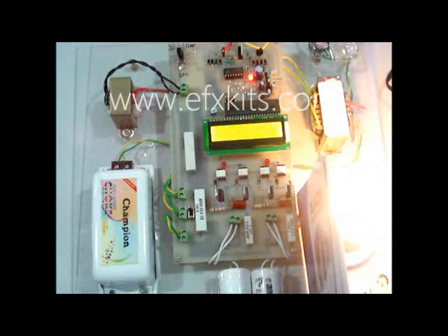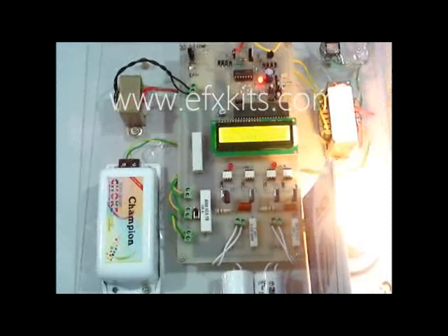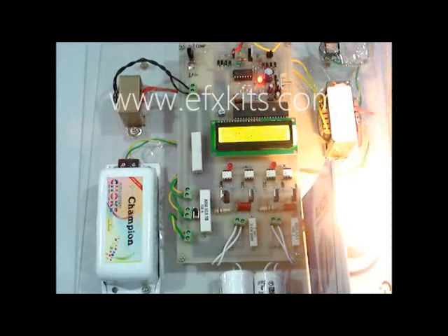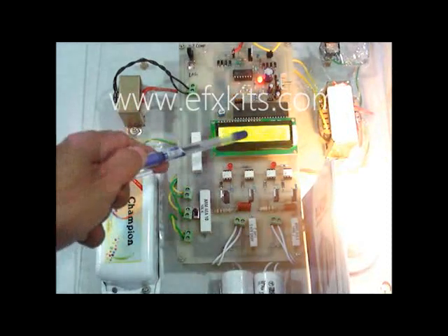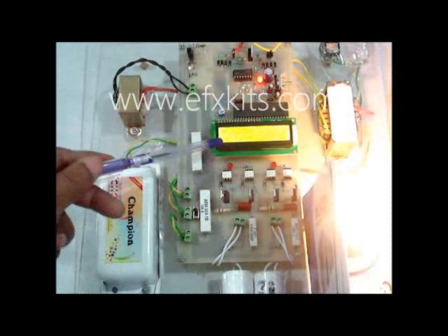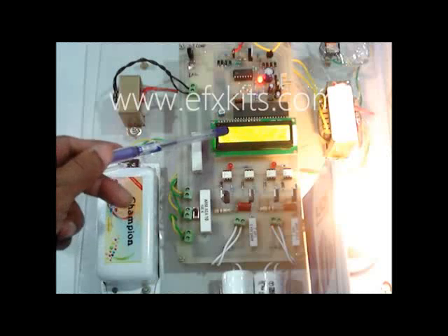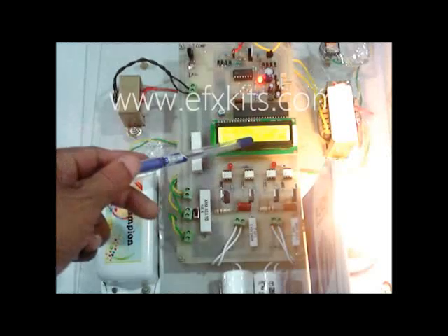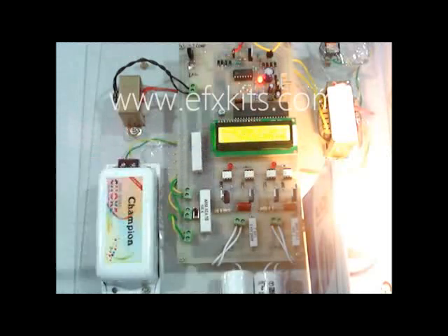you can see the reading, that is SVC, FACTS project thyristor switched capacitors, as you can see on the LCD, and now it gives me a reading of 0.728, that is the power factor, and it tells the time delay between the voltage and the current. The power factor is this, and the time delay between the voltage and current is 2.385 milliseconds.